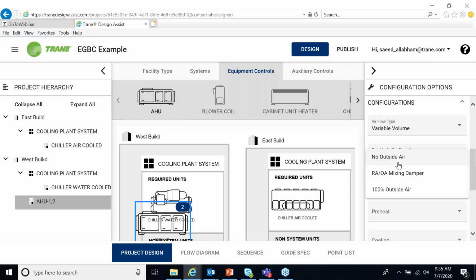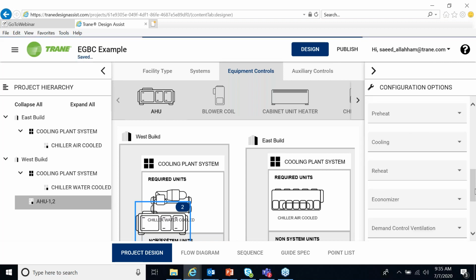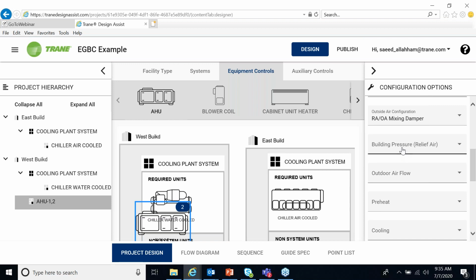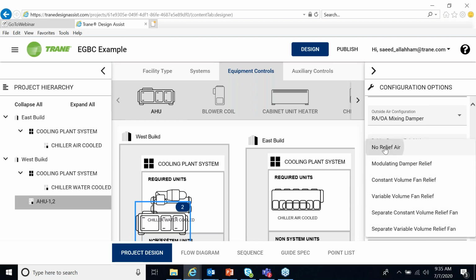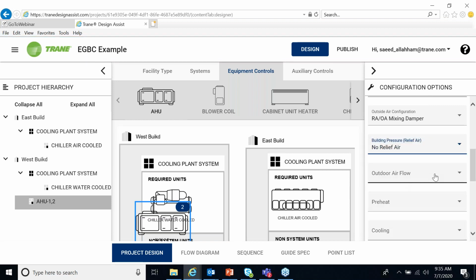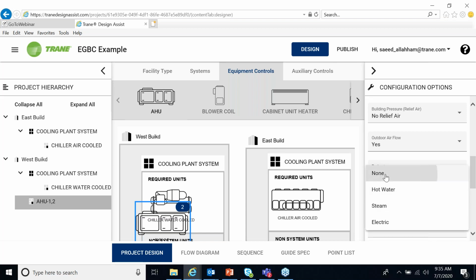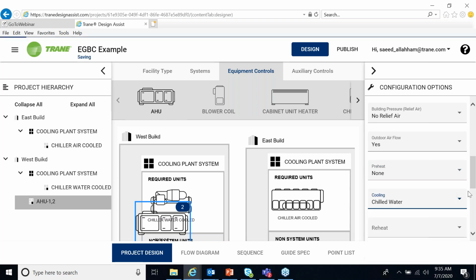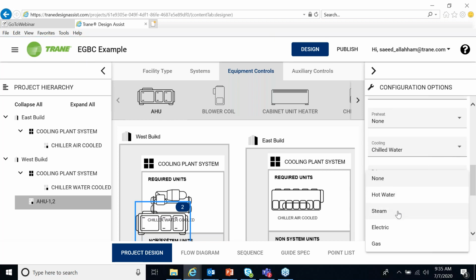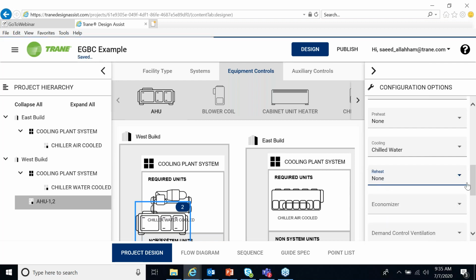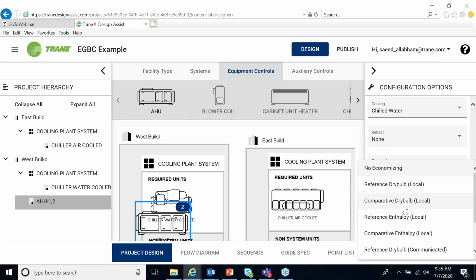Outside air configuration, if we have outside air, fresh air 100% or mixing, let's select mixing. Building pressure relief, let's say no relief, that the relief is done separately, not by the AHU. Outdoor airflow, yes, we have outdoor airflow. A preheat, we don't have preheat. Cooling, what is the type of cooling? Chilled water or DX, let's say chilled water. Reheat, let's say we don't have reheat now. Economizer, let's make it simple and make it no economizer.